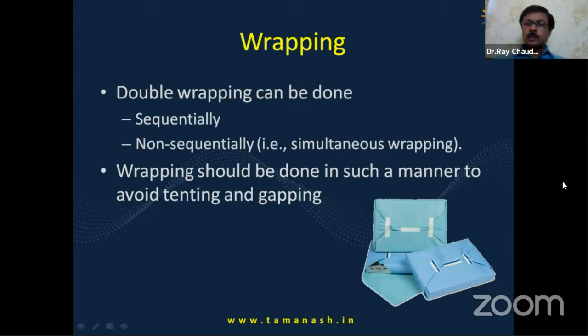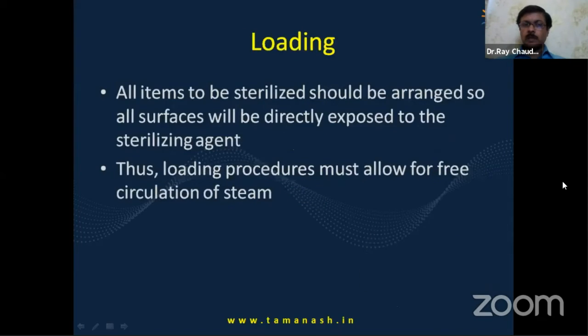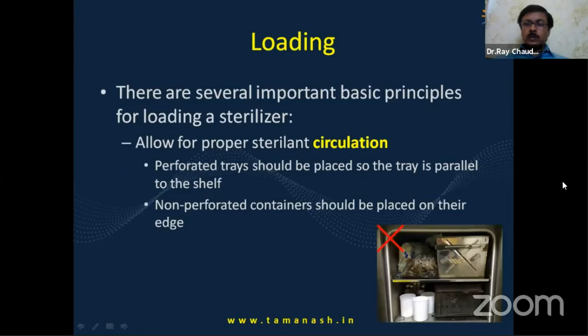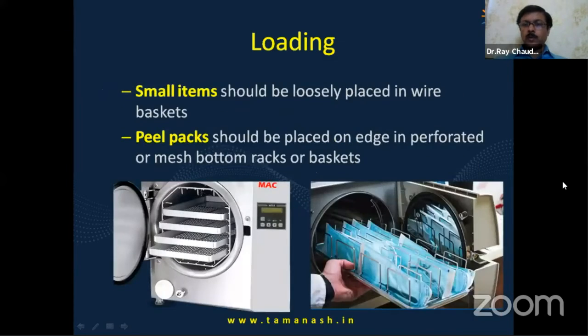So first you wrap once and then you take another wrap and wrap it twice, not both wrapped twice simultaneously. Loading process must actually allow, the only common sense that has to be applied is that there must be adequate space so that steam can percolate. So this is a wrong way of putting the loading. This is the correct way. So small items should be placed in wire baskets or perforated trays as is shown in the left of your pictures, and peel packs should be placed on edge vertically so that one flat surface is not in contact with the tray.